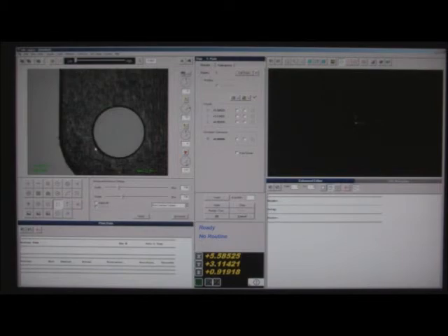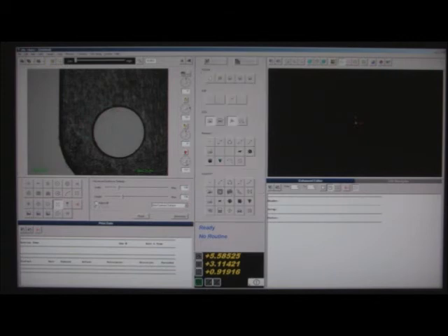And when I talk about more accurate, it may increase it by 50 millionths or 1 micron more accurate than the standard focus, but it does give us that little bit. The downside to this is that the standard focus takes about 1.5 seconds, and this takes another second to run in the program. So you're looking at about 40% more time for that target to operate than the next one.